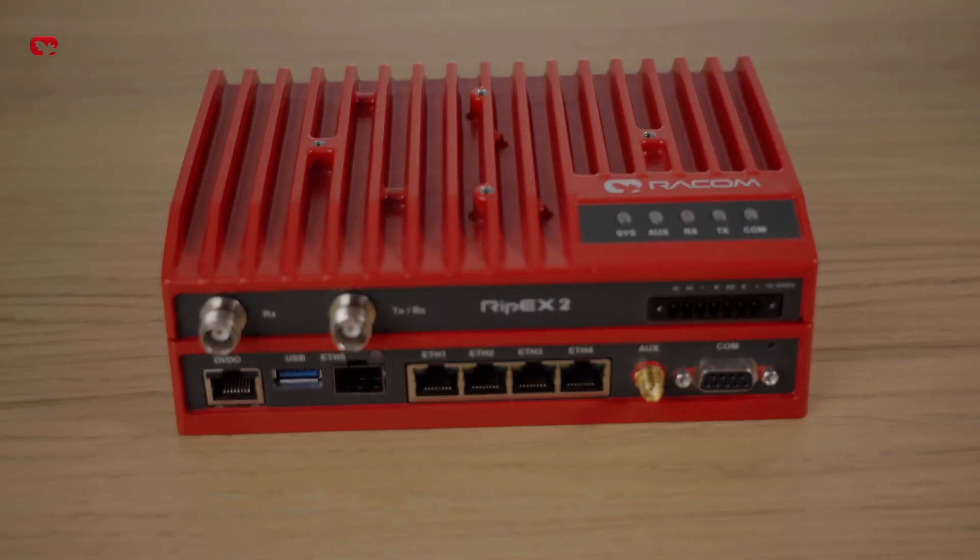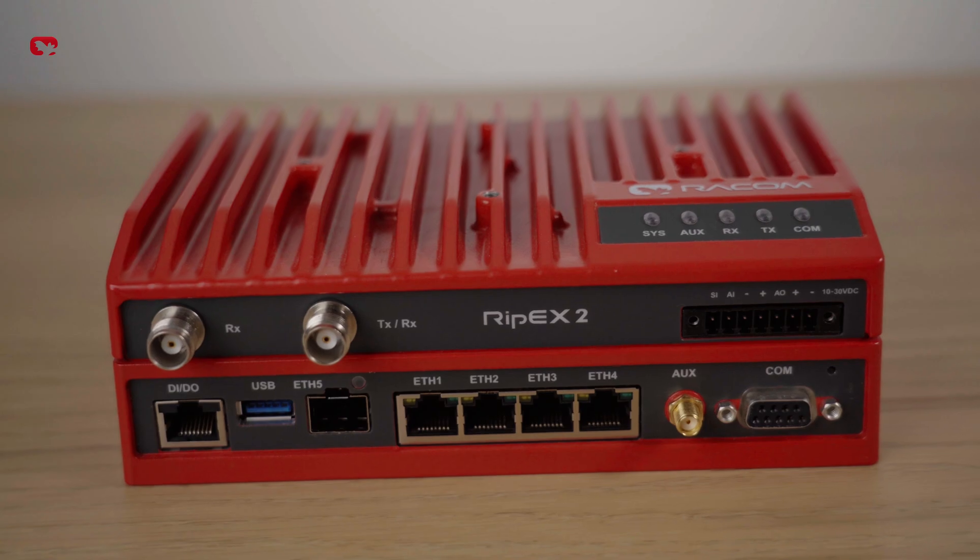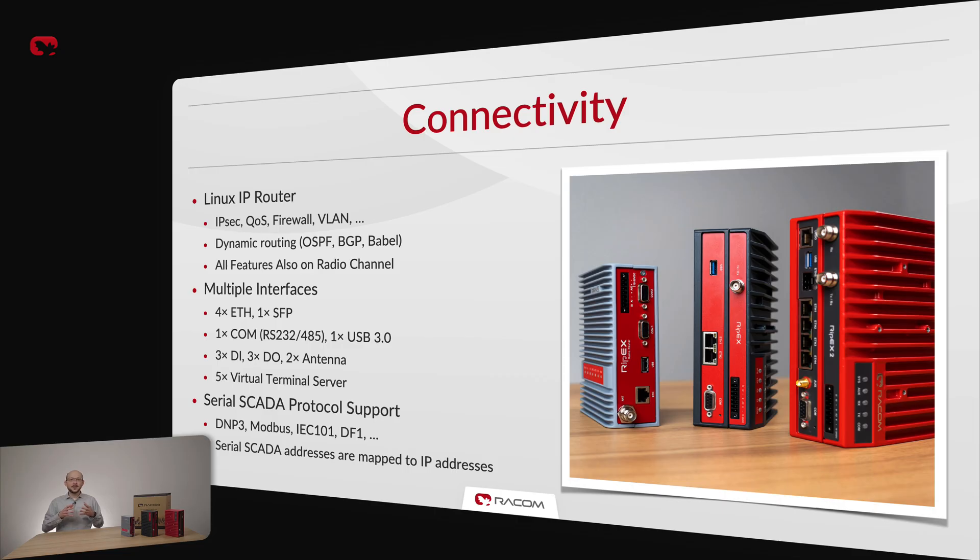Five ethernet ports can be independently set in switch or router mode or a combination of both, while the SFP port enables direct fiber-optic connection. The USB port is used for out-of-band management either directly or wirelessly via a Wi-Fi adapter. The same serial SCADA protocol software drivers and terminal servers used in the original RIP-X are implemented, so legacy serial RTUs can be simply connected to the IP world via RIP-X. Additionally, a combination of serial and IP protocols like Modbus RTU and TCP or DNP3 serial and TCP within one network is possible.